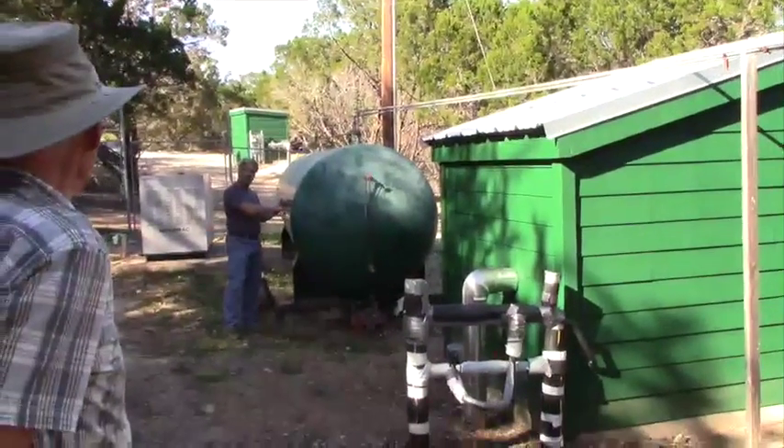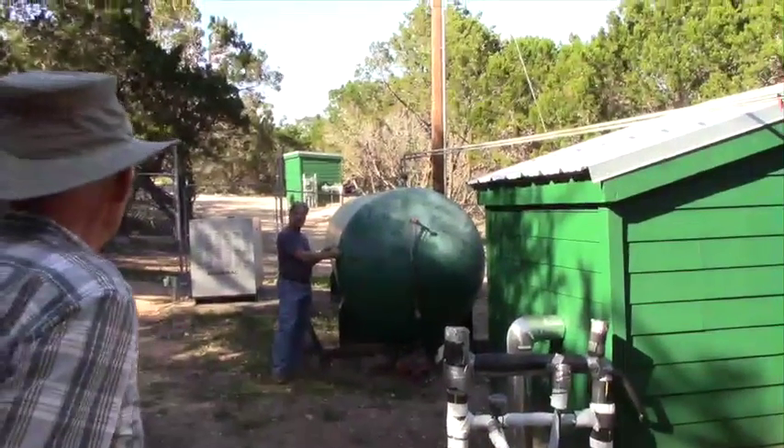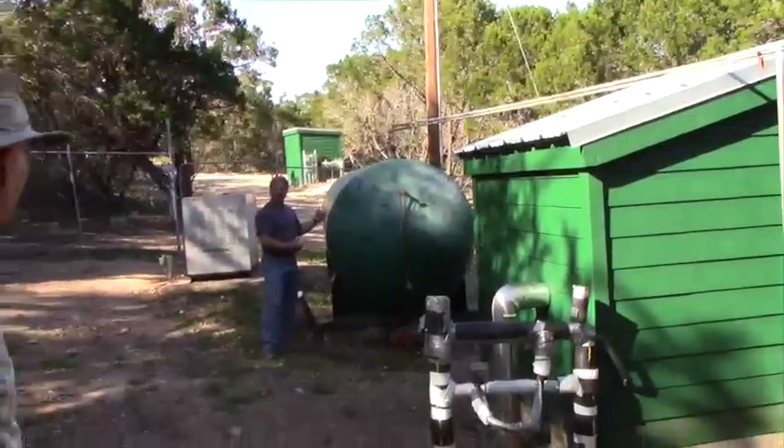We do get some circulation through here. The concern is about chlorination residual — water could get stuck in this tank. If the tank basically feeds the line out, how do we know we get turnover inside?